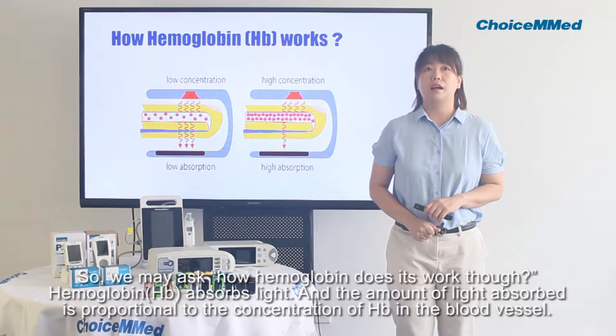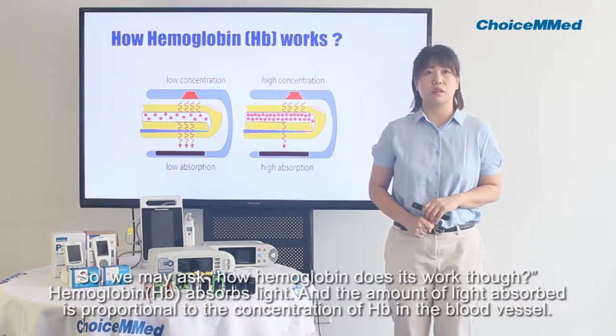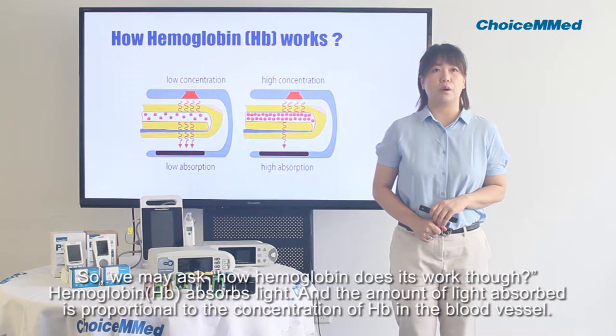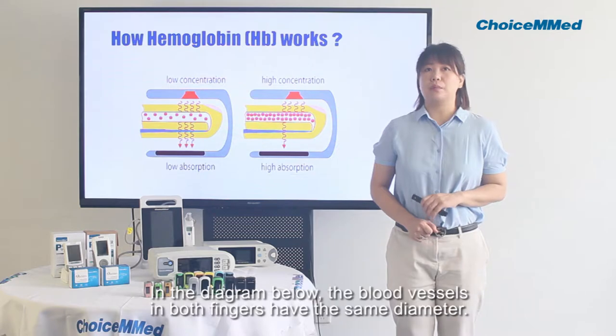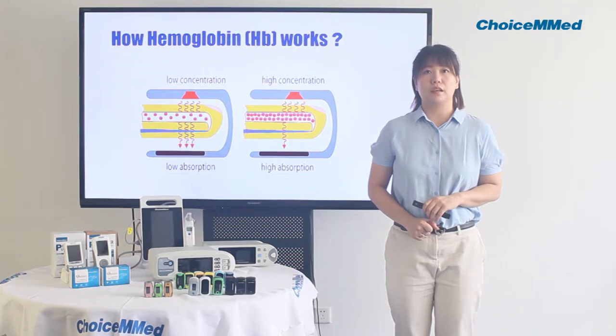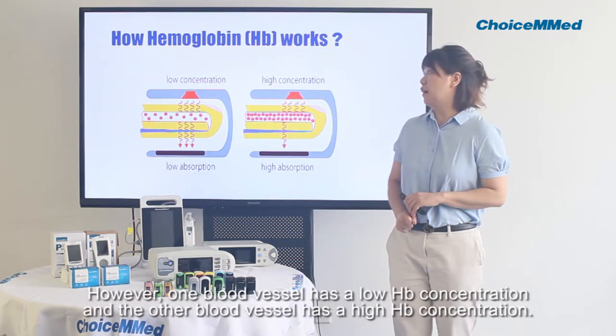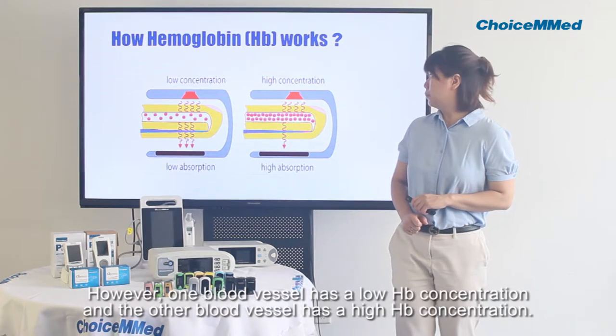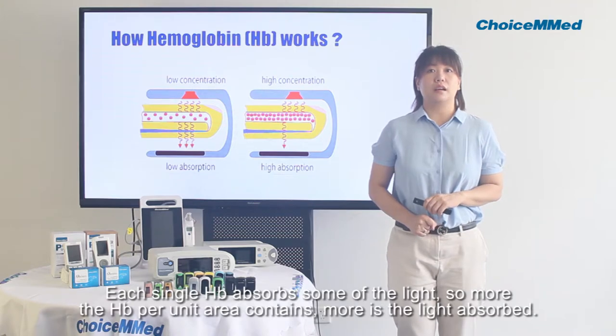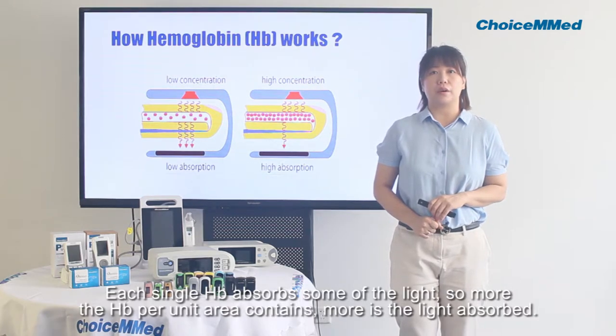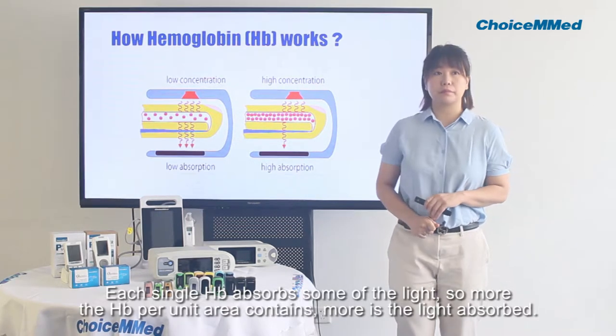So we may ask, how does it work? Hemoglobin absorbs light, and the amount of light absorbed is proportional to the concentration of hemoglobin in the blood vessel. In the diagram below, the blood vessels in both fingers have the same diameter. However, one blood vessel has a low hemoglobin concentration and the other has a high hemoglobin concentration. Each single hemoglobin molecule absorbs some of the light, so the more hemoglobin per unit area, the higher the light absorbed.